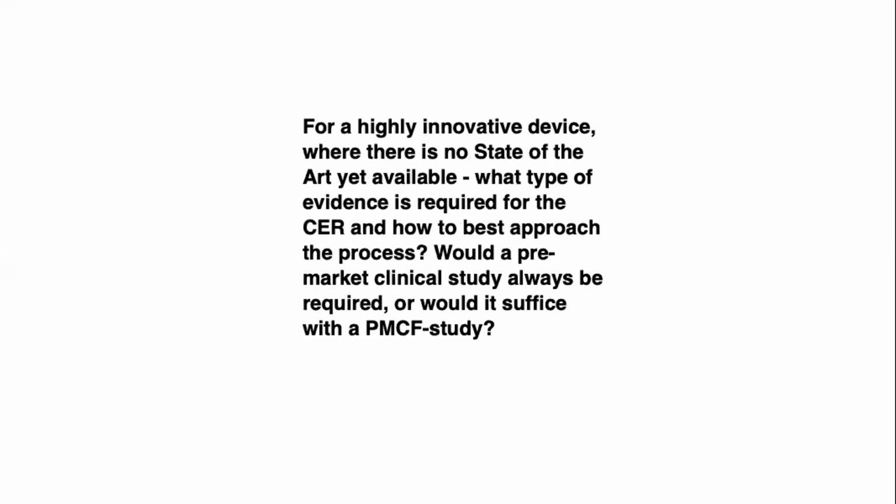So what is the best approach? What type of evidence is required for the CER for your highly innovative device? If it's post-market, then you would use the usual clinical data sources: any clinical literature that's been written about it, any clinical investigations that were done on it or are ongoing, any PMCF data you may have on it, and any PMS data that you have passively collected as part of your PMS activities.